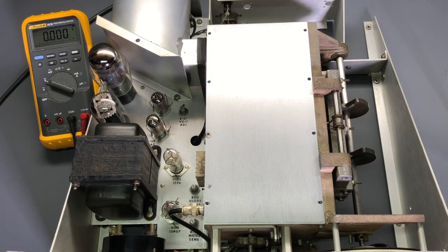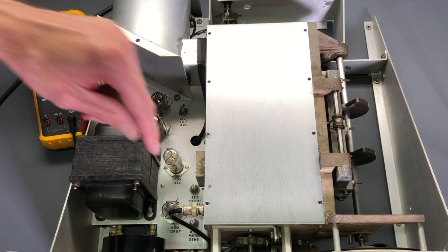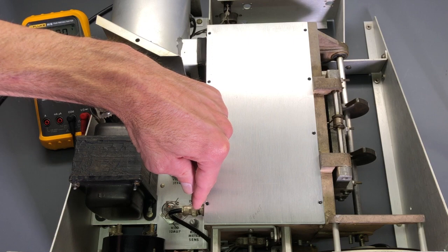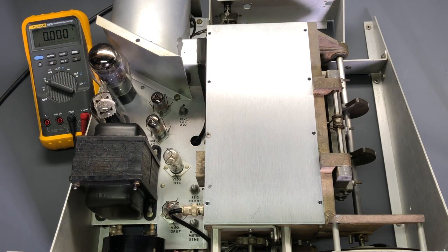so no further issues. Now, you can see down here on the lower part of the chassis, there's R125, the meter sensitivity adjustment, that variable resistor down there. And that needed some slight adjustment to compensate from the lowest frequency extreme, 10 megahertz, up to 500 megahertz. If you set it so that it's spot on, say at 15 megahertz or somewhere in the lower frequency ranges, by the time you hit 500 megahertz, there was a little more error than I wanted to see. So really just a balance between those two extremes, and the reading on the meter is very acceptable at this point. So again, no further issues.